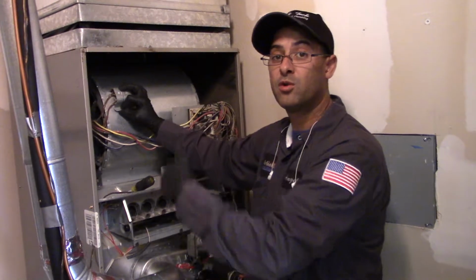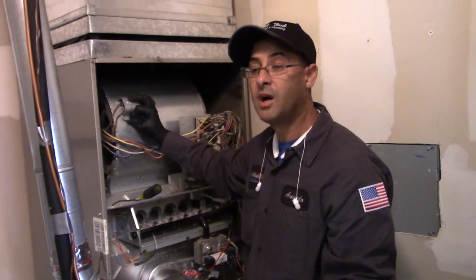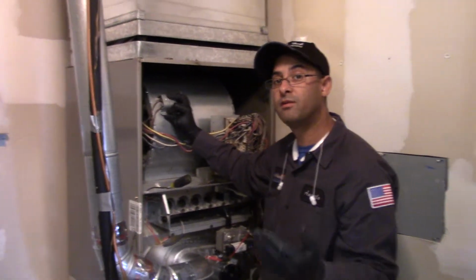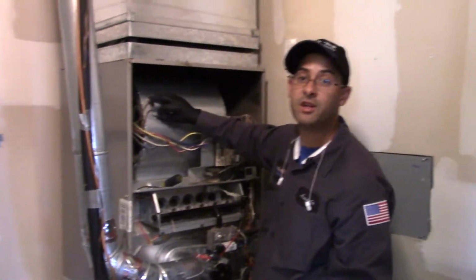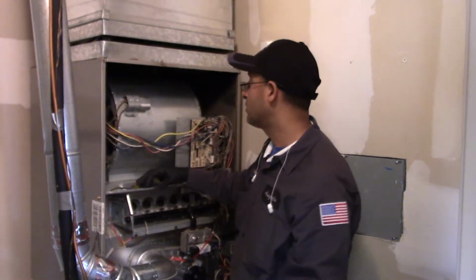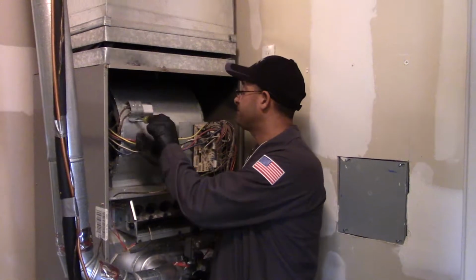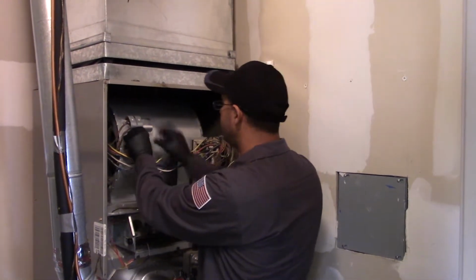So we would have to let that motor cool down before we can see if it's going to work. But in order to see if it's going to work, we've got to make sure that the capacitor is good. So the way we check these capacitors, I'm going to go ahead and remove it.